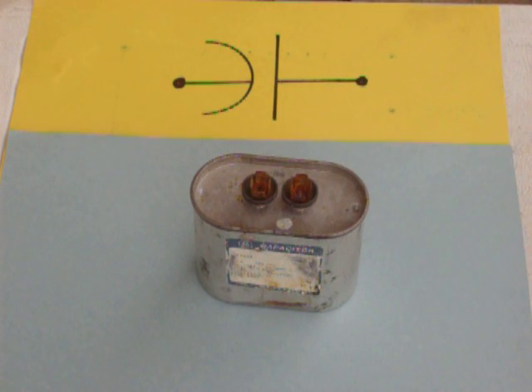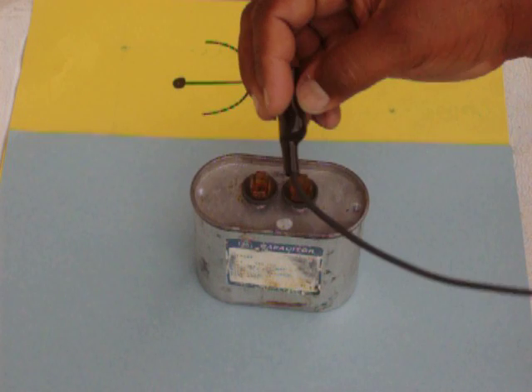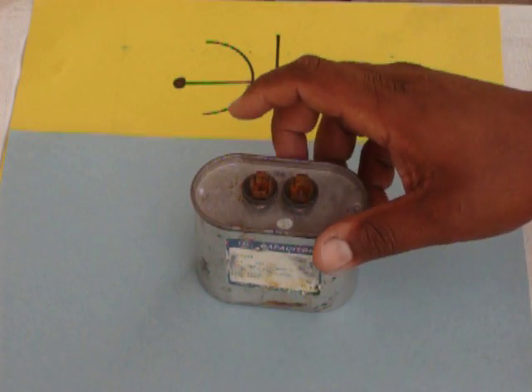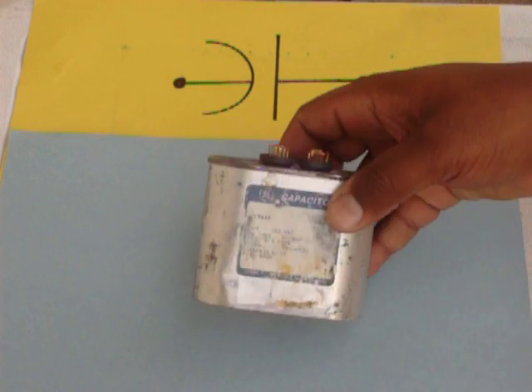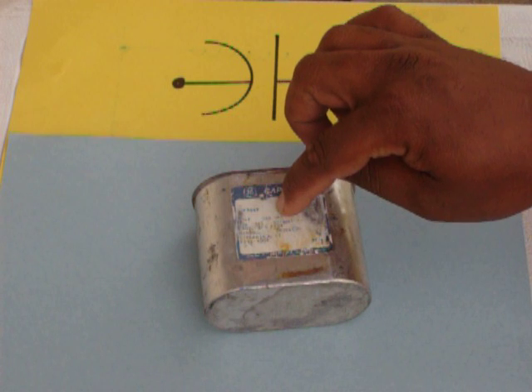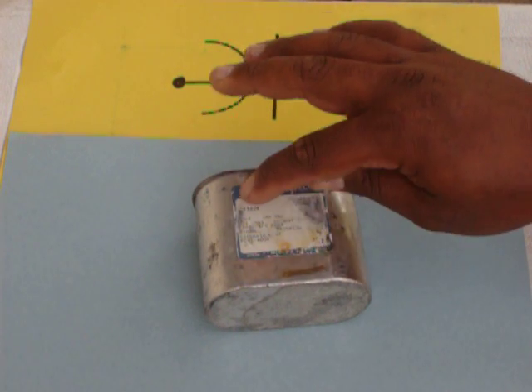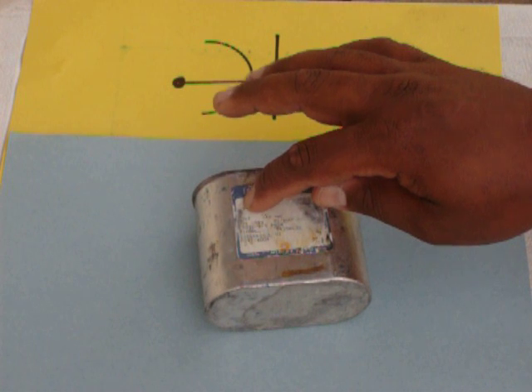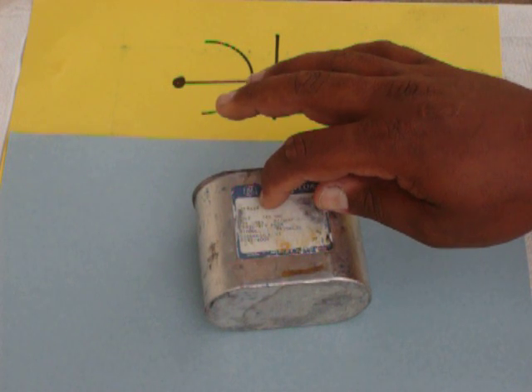Most people just take a screwdriver and short out these two terminals. After you do that, the next thing you're going to do is find the rating of the capacitor. This is a 35 microfarad by 440 volt. You need to find those two numbers, the microfarads and the voltage. Your microfarads are either going to be labeled MFD or UF.